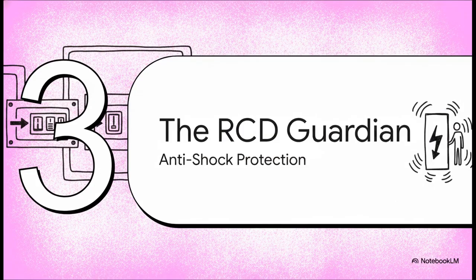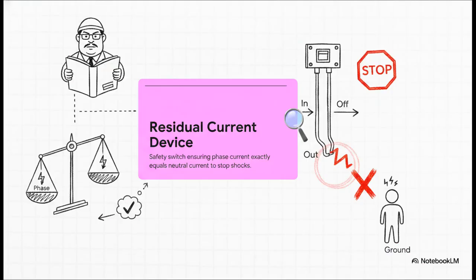Which brings us to Section 3, the RCD Guardian. This is your ultimate anti-shock protection. So, moving past that main manual switch we talked about, we hit our first real inner defense inside the consumer unit: the residual current device, or RCD for short. I want you to think of the RCD as a highly strict accountant who is just constantly balancing a ledger.